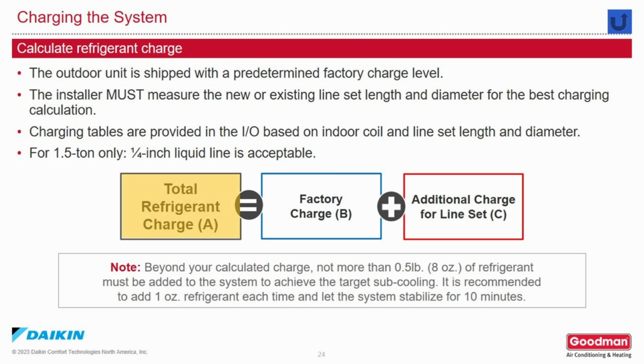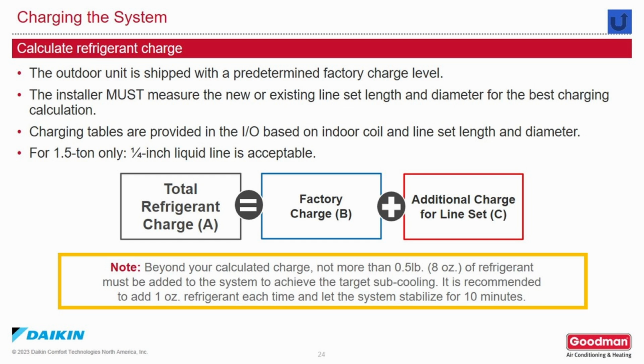The total refrigerant charge is equal to the factory charge, which is listed on the data tag of the unit, and the additional charge, which you will calculate by line length and line diameter, from the installation manual. After the final charge is calculated and installed, you should not add more than 1/2 pound or 8 ounces of refrigerant in order to achieve your target subcooling. If you're having trouble getting that target subcooling, we recommend that you add 1 ounce of refrigerant at a time and let the system stabilize for 10 minutes before adding more to prevent overcharge.